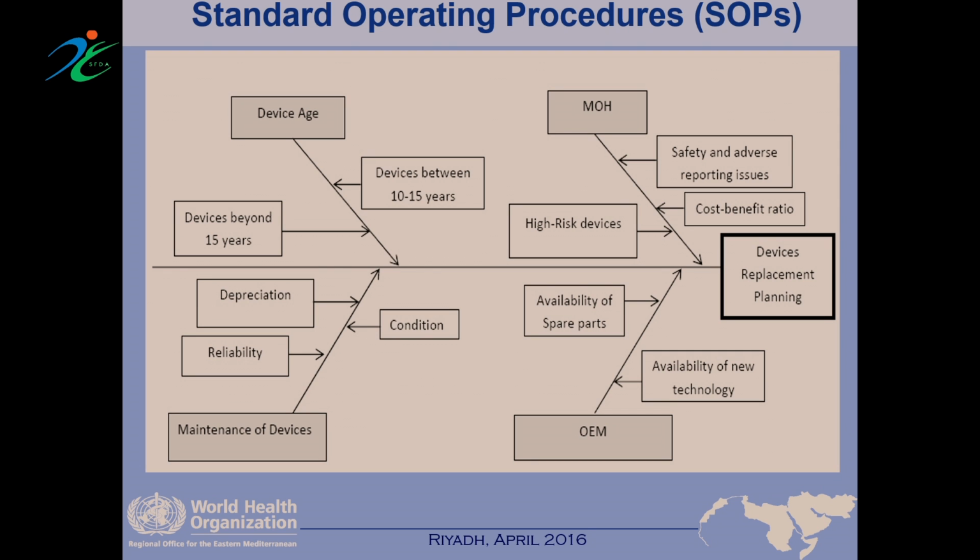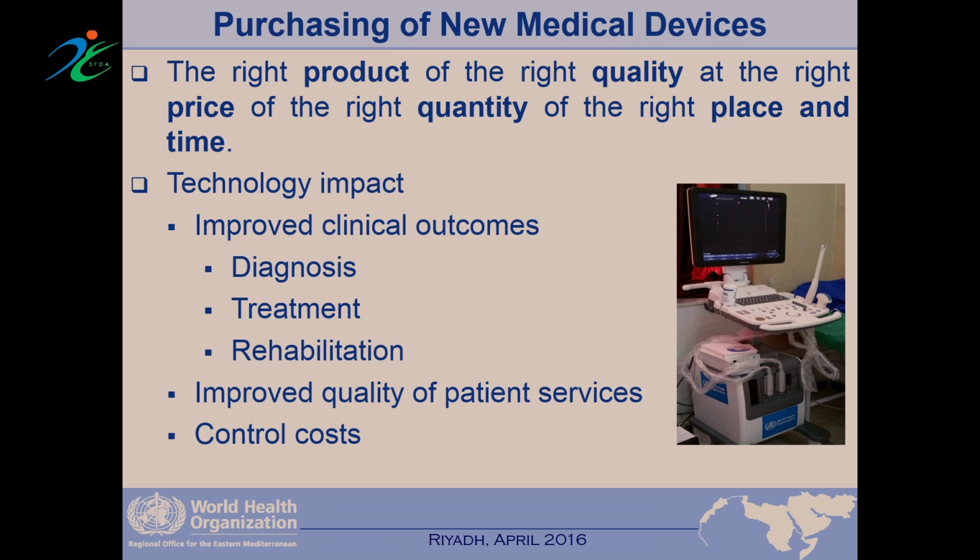So you might consider that when doing your inventory, or even procurement. Once you procure equipment, there are kinds of guidance for each piece of equipment. There is an age, or how we call it, a life age for those equipment. Particularly for, let's say, a ventilator, the expected life for those equipment is between 8 to 10 years. So if you are doing your preventive maintenance and you have a fully functioning system in place, you ensure that before those equipment reach that age, you have a replacement system in place to tackle those items, and then you try to purchase ahead of time those kind of equipment needed.